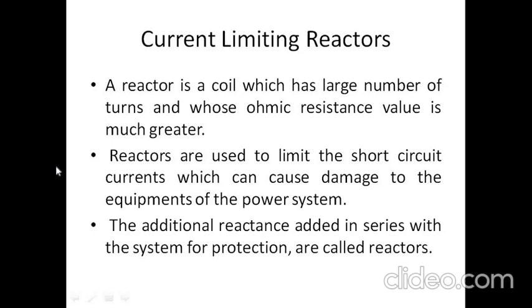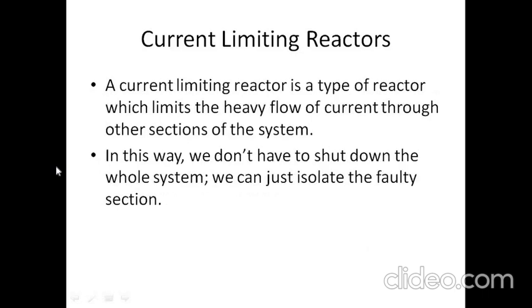Under abnormal conditions when a fault occurs, the fault current magnitude is very large. Our protection system and whatever protective switchgear we are using must be capable of handling this large amount of current. To reduce this fault current magnitude, we are going to use this reactor coil. The current limiting reactor is a type of reactor which limits the heavy flow of current through the other sections of the system.